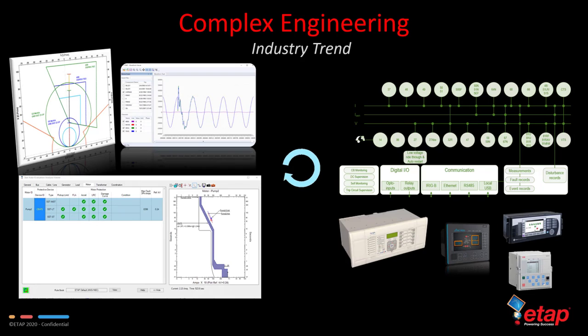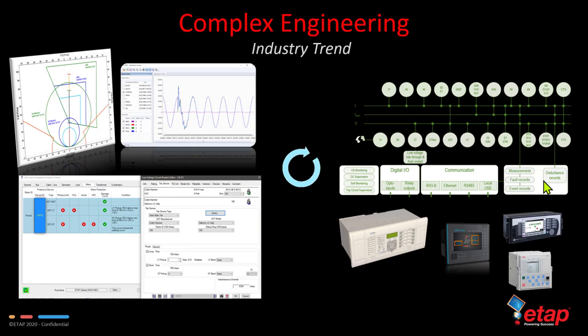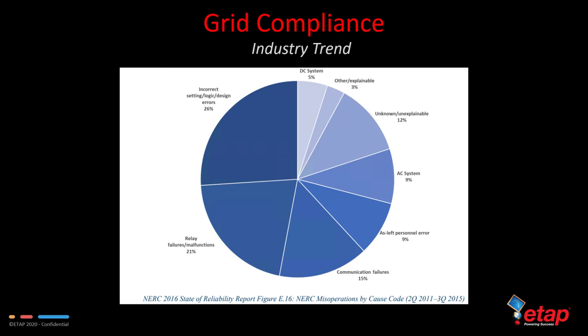For example, it is possible to read the fault signature from a relay, determine the fault type, location, and play it back into the analysis program to determine the as intended operation. You can then compare it with the as designed and as operated conditions to determine a measure of success for your protection scheme. Another industry trend is towards grid compliance.